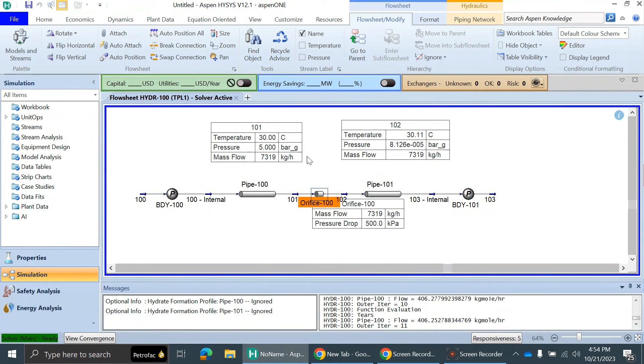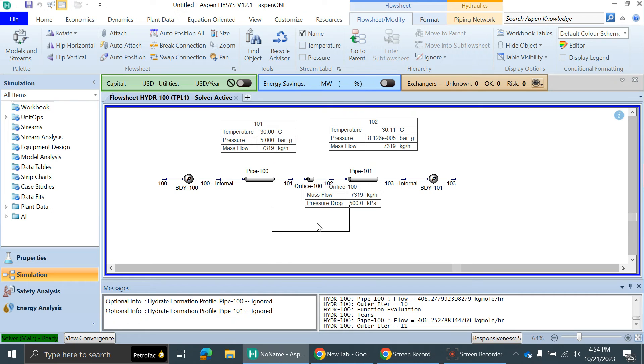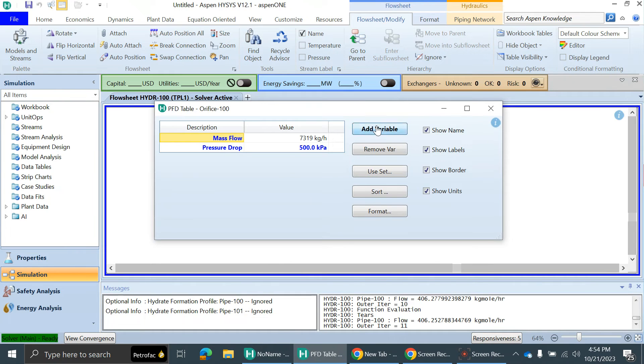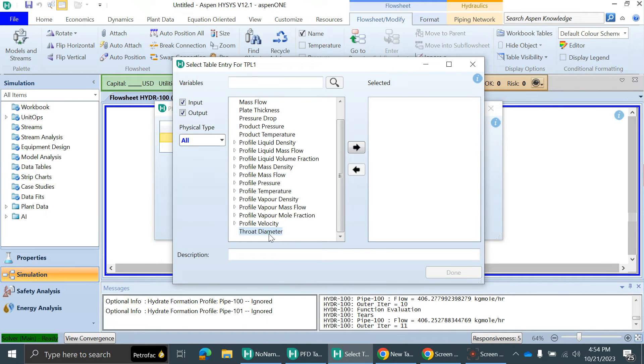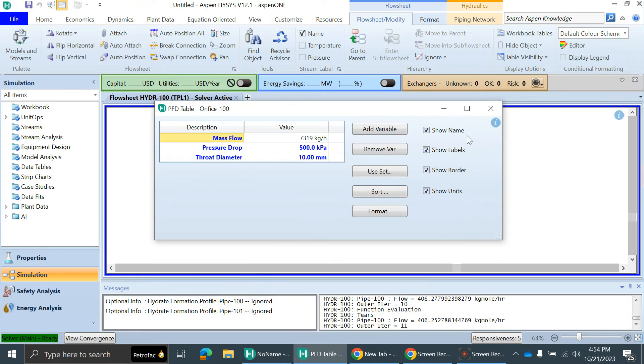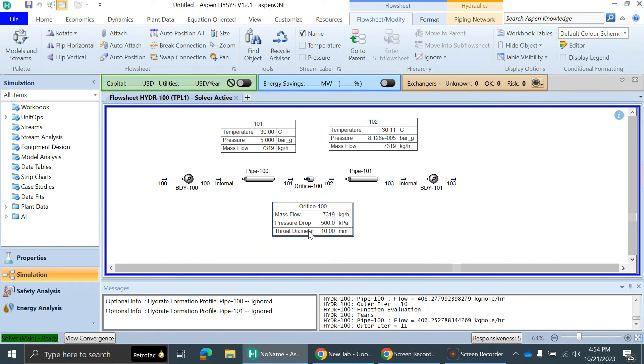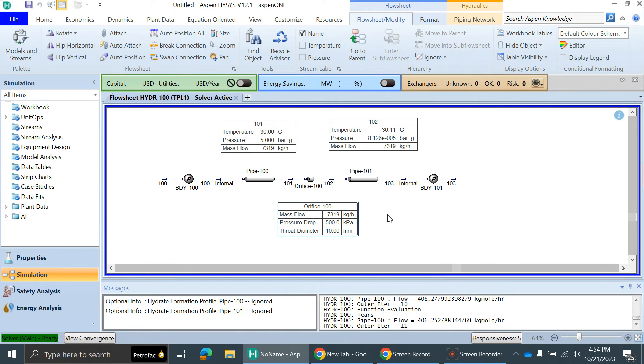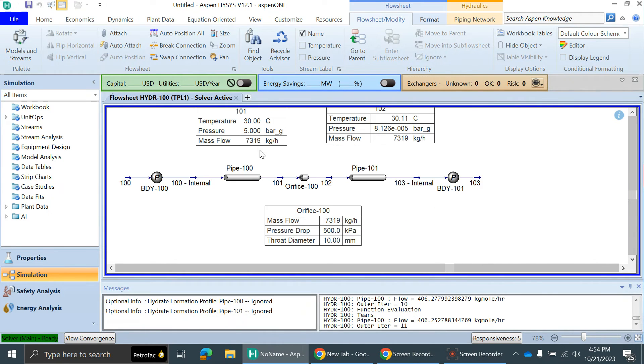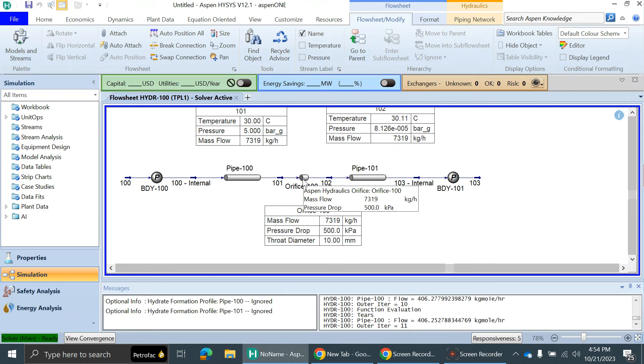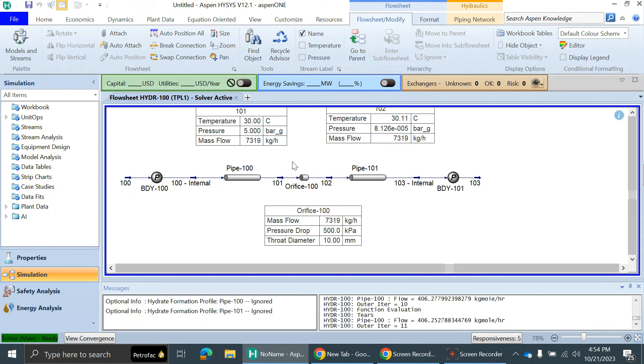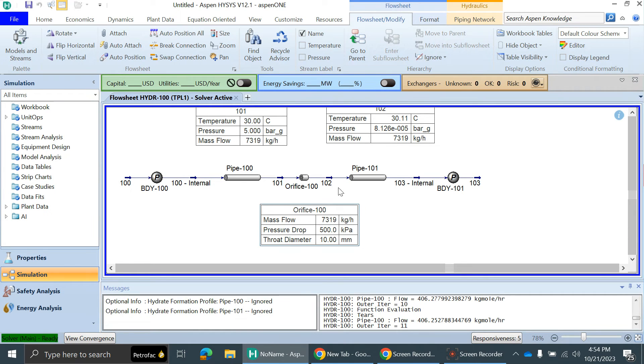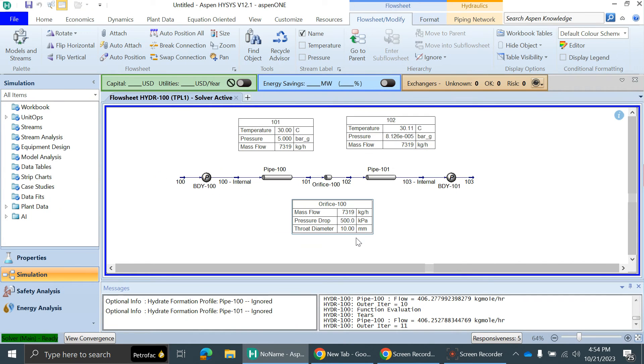You can see at this much delta P, I'll also show the table for the orifice. You can also add the throat diameter in the table. You can see the pressure at the orifice inlet is 5 bar gauge and outlet pressure is almost 0 bar gauge. This much flow can pass through this orifice: 7319 kg per hour of water. These are the orifice details: the pressure drop across the orifice is 500 kilopascals and the throat diameter is 10 mm.